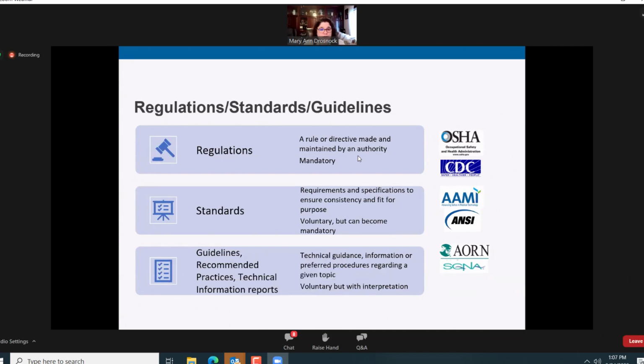Then as far as where the standards organizations fall, these are things like ANSI, AAMI. We have our national standards. Although they are considered voluntary for a facility to follow, they do become mandatory if your facility or your department states compliance with AAMI standards. Then it's expected that you do follow them, and you can be surveyed and inspected to those standards then. So within ST91 and other standards like ST79, we have requirements and specifications that by following the standard, you ensure that you have a consistent process in place.